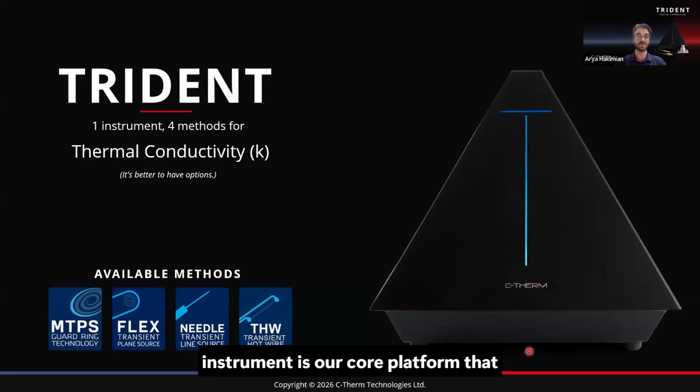Our Trident instrument is our core platform that offers 4 different methods for thermal conductivity testing, depending on the type of sample, the size of the material that you have available, or the conditions you're looking to test under. This can all dictate which method is most appropriate. We're going to go through that here today and talk about that as it relates to the concrete samples.